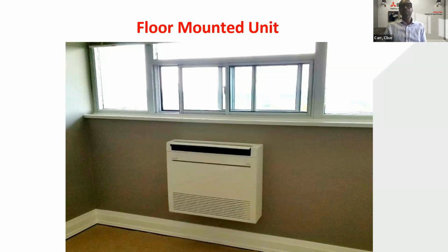They're looking at the cost of electricity, the outside temperature, the efficiency of both equipments, and the demand on the equipment, placing that into an algorithm and seamlessly in the background, transitioning into operation between the gas furnace and the air source heat pump, or whatever other secondary heating source that you're using. The algorithm that's built into the smart thermostat would do the fuel switching between the system, leading you to the ultimate energy efficiency and operating cost of your system.